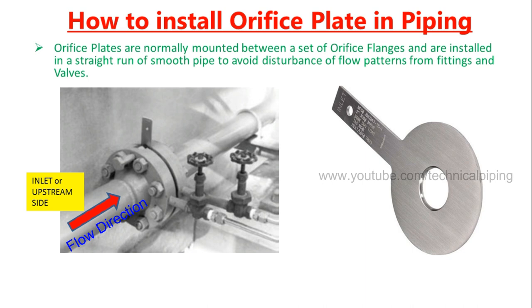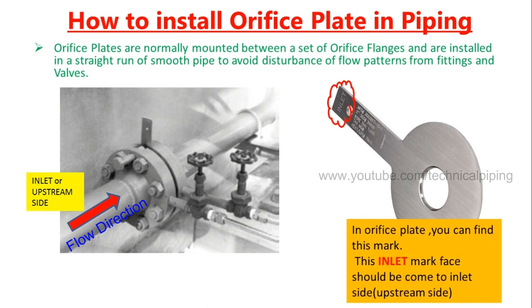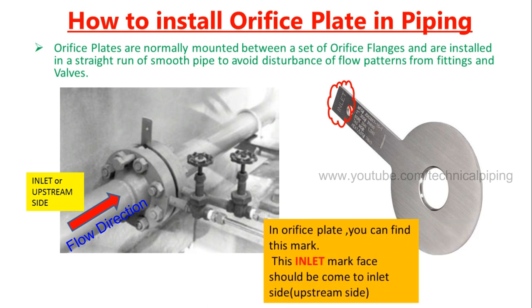This pictorial view clearly explains the installation of the orifice plate between the orifice flanges. On the orifice plate, you can find an inlet marking. At the time of installation, this inlet-marked face should face the inlet side. Based on the pipeline flow direction, you can finalize the inlet of the orifice plate.